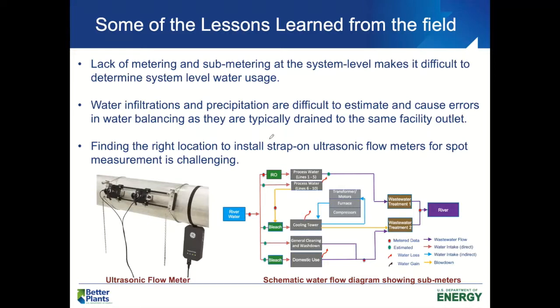One caveat to note is that ultrasonic flow meters are really good to work with and give good, accurate measurements, but finding the right location for them could be a little tricky. They have specific criteria you need to hit for them to work properly — they shouldn't be close to elbow bends, and the water flowing through the tube should be clear and fully formed for them to get accurate measurements. Those are things to keep in mind when using this equipment.